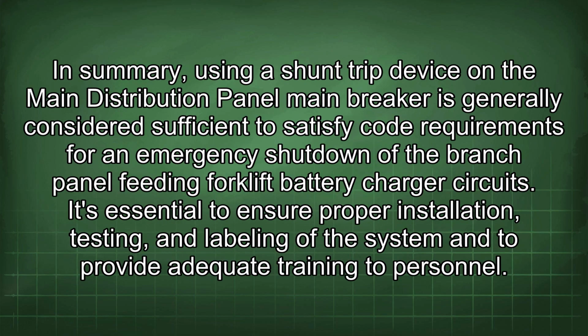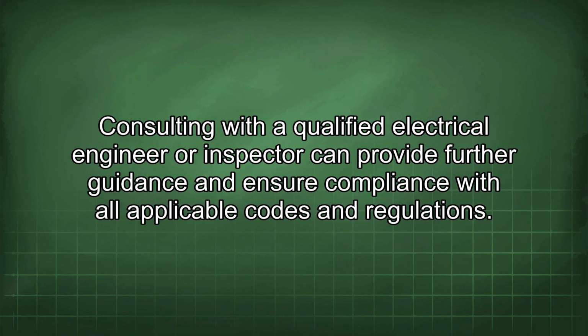In summary, using a shunt trip device on the main distribution panel main breaker is generally considered sufficient to satisfy code requirements for an emergency shutdown of the branch panel feeding forklift battery charger circuits. It's essential to ensure proper installation, testing, and labeling of the system and to provide adequate training to personnel. Consulting with a qualified electrical engineer or inspector can provide further guidance and ensure compliance with all applicable codes and regulations.